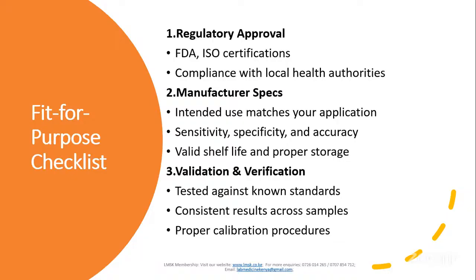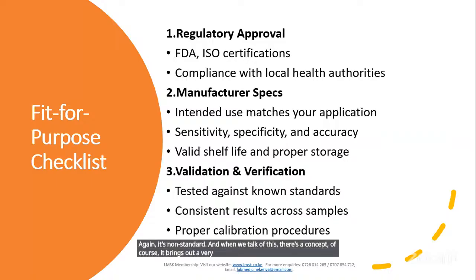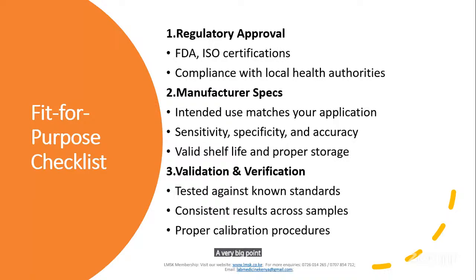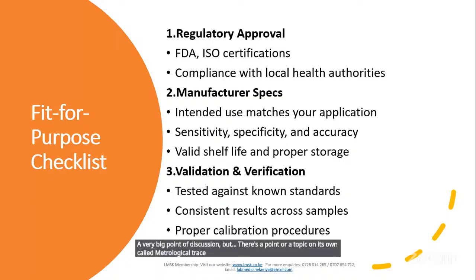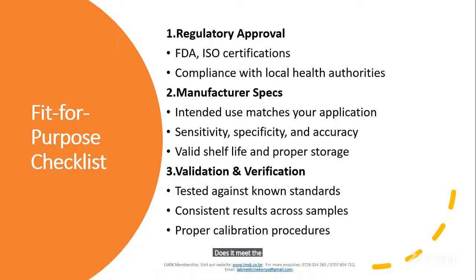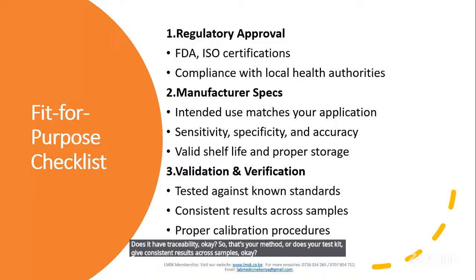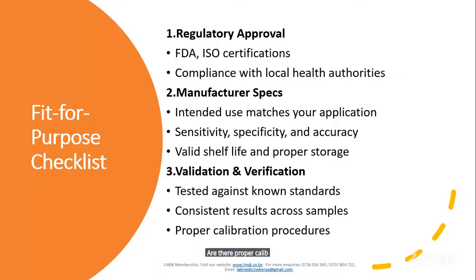Has this kit or methodology been tested against known standards? When we talk of this, there's a concept that brings out a very big point of discussion, a topic on its own called metrological traceability. Does it meet the standards? Has it been tested against known standards? And did it pass? Does it have traceability? Does your method or test kit give consistent results across samples? Are there proper calibration procedures in place for this kit or methodology?